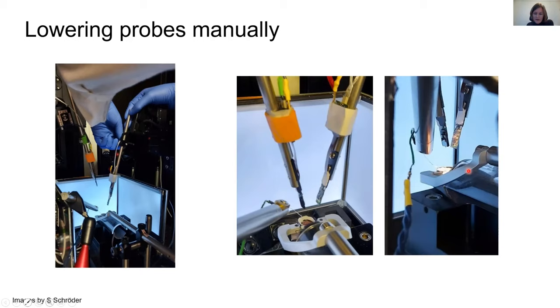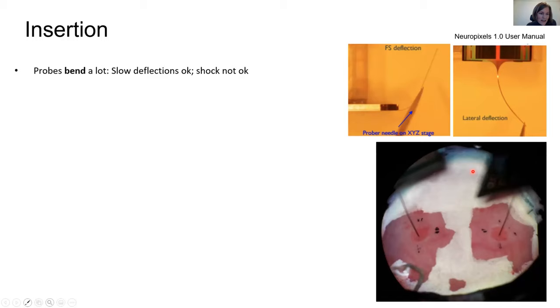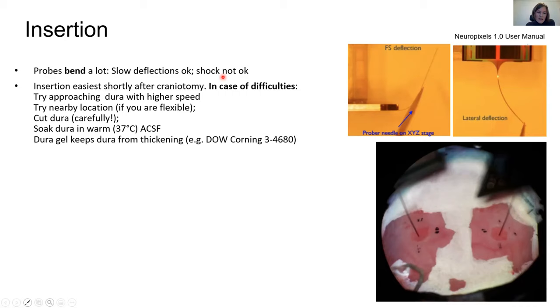Now a few words about the insertion. Most likely your probe will bend when you try to insert it. This looks pretty scary, but you shouldn't be scared because these probes are extremely flexible, so if you deflect them slowly that's totally okay, they can take it. You should just not make sharp movements, so then they can actually break.